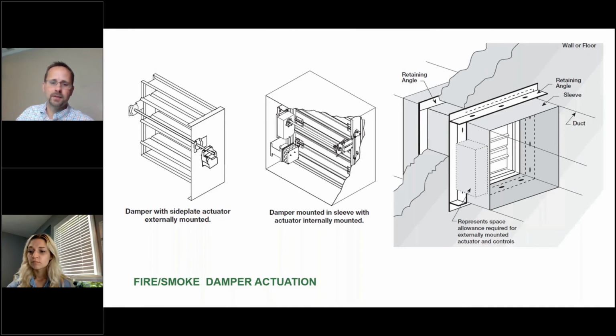So there are also a couple of different options for the actuator. Number one, the actuator needs to be coordinated with the voltage. Typically, in my experience, we've always done 120 volt unless the owner wants a lower 24 volt, or pneumatic actuators. I've had some owners who prefer 24 volt so that their own maintenance people can do maintenance. They don't have to have a certified electrician come there to do maintenance on those actuators. So that's a good reason to do that. But again, the voltage needs to be coordinated, and the transformer needs to be coordinated in the field as well.